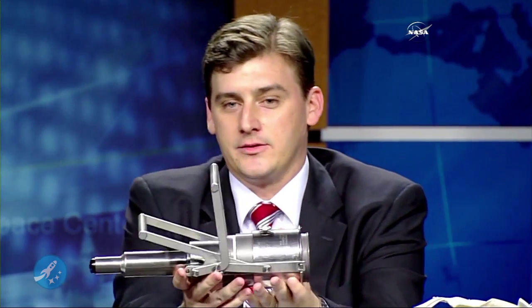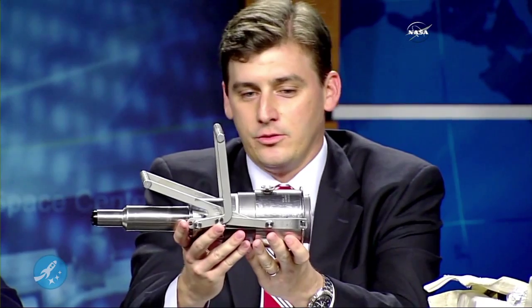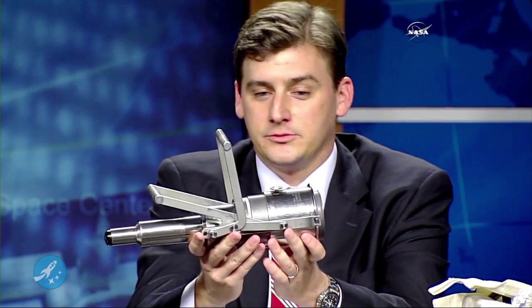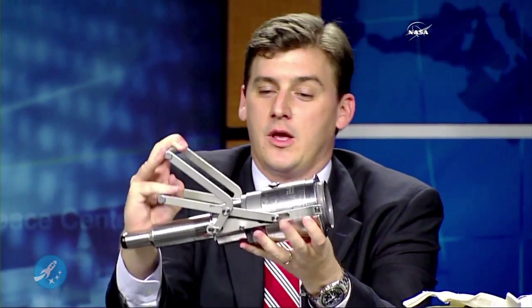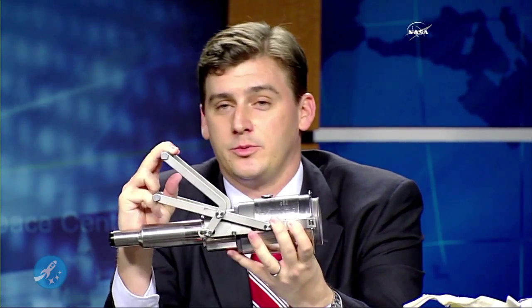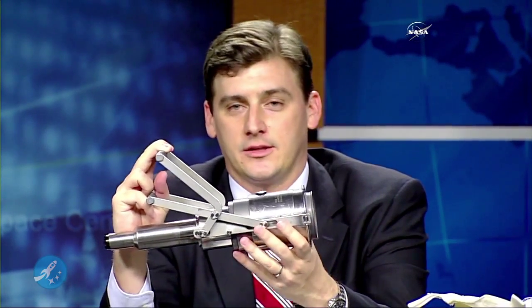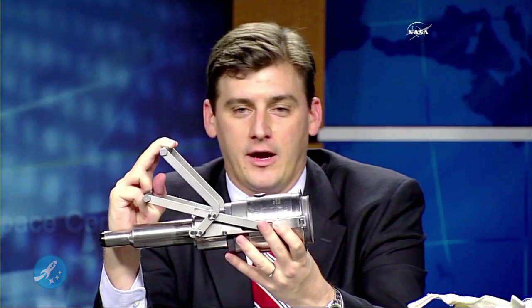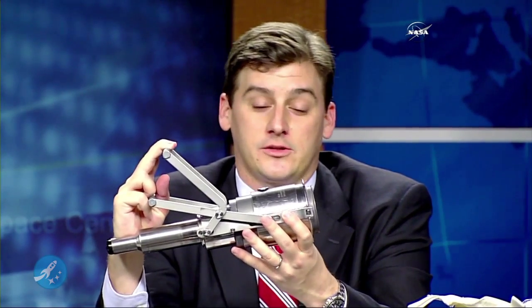To describe a little bit about what happened and what went wrong: this is a one-and-a-half-inch quick disconnect. This is similar to three of the four quick disconnects the crew was interacting with today. The other two of this size demated without much problem at all. These are known to be somewhat tricky sometimes, and I'll show some motion of this. Basically, this is going towards the valve closed position, and what can happen — the first time we came to the closed position, we saw a little bit of a leak. The troubleshooting for that: we don't want to demate this and have a leak going constantly if it's from the female side.